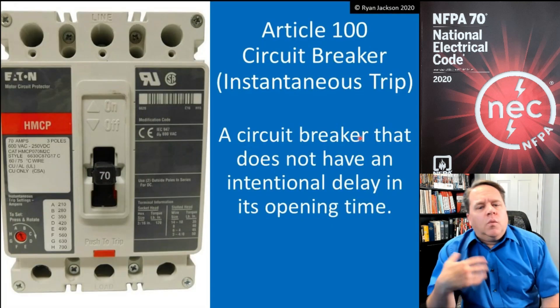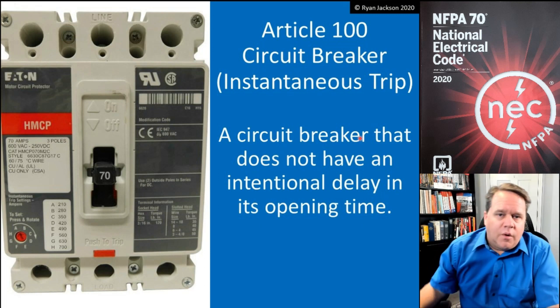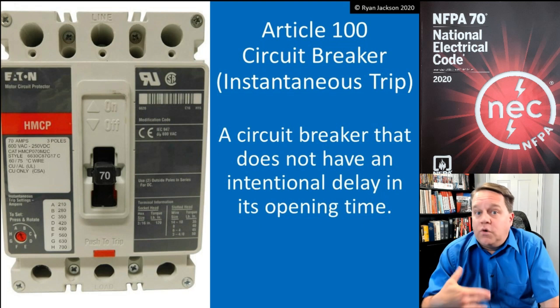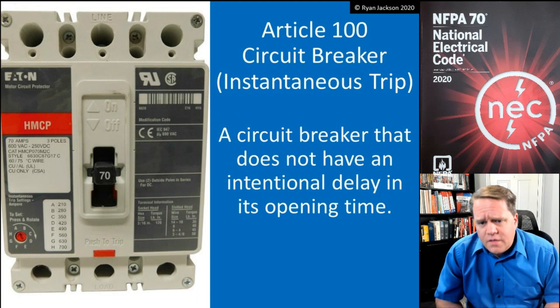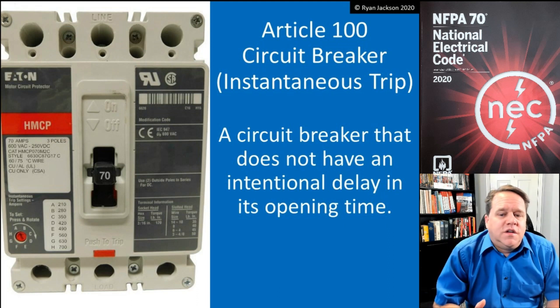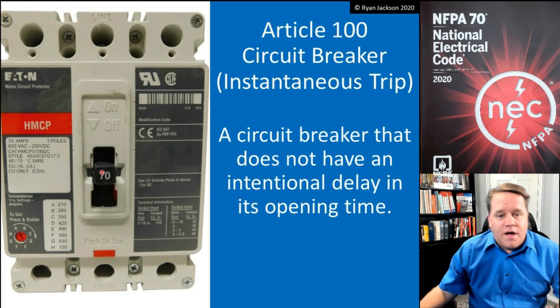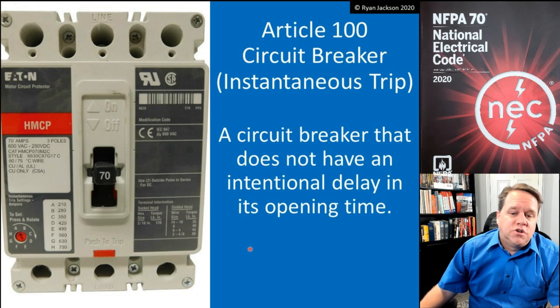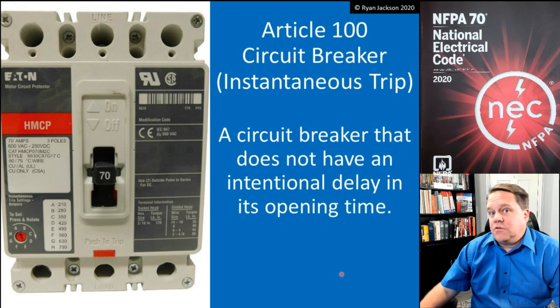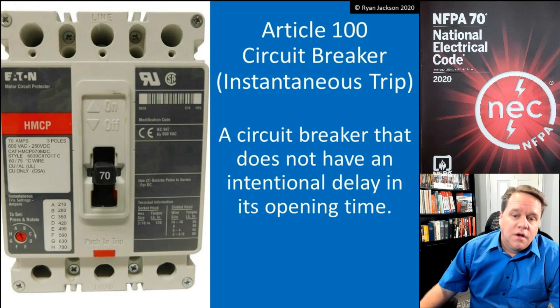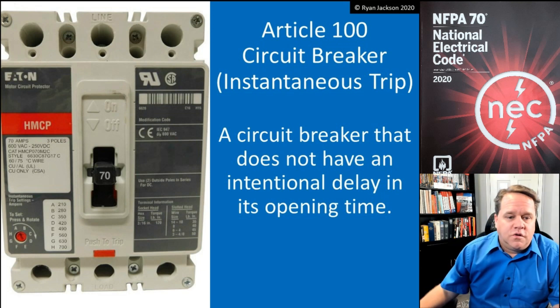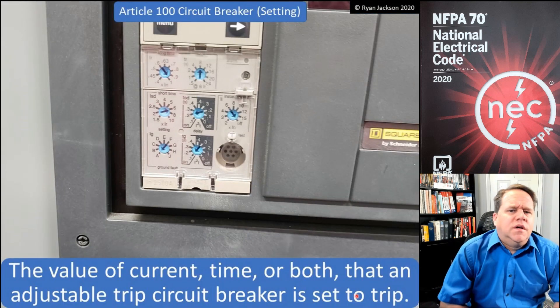We also have instantaneous trip circuit breakers. This is not something used in a general application — you won't find it in your house. It's a circuit breaker that does not have an intentional delay in its opening time. When it hits, say, 70 amps, it trips right there. It doesn't really have a time-current curve because it's not an inverse time circuit breaker — it's just instantaneous: when it hits the opening current, there is no intentional delay.